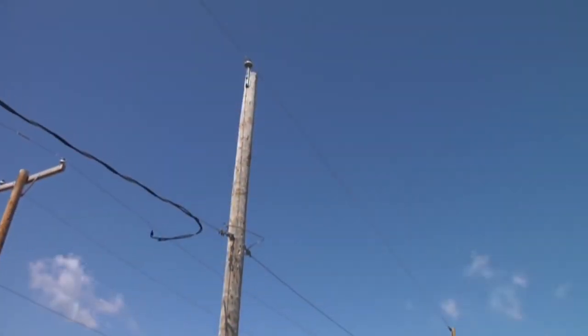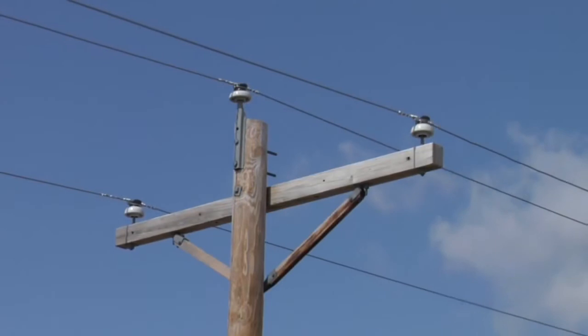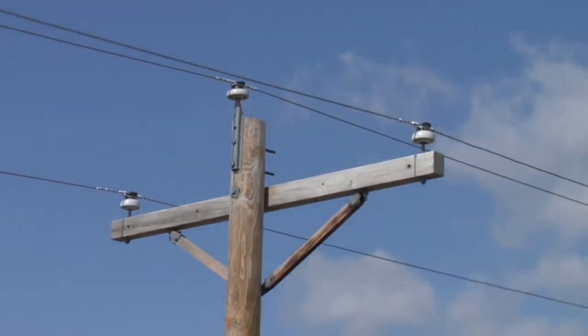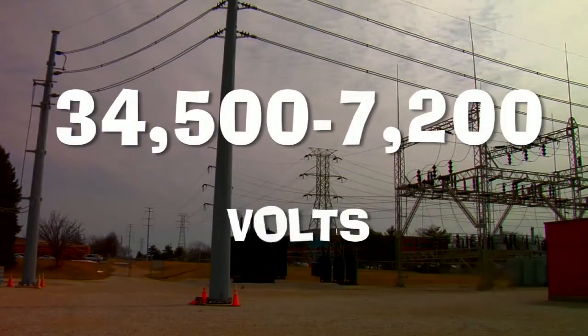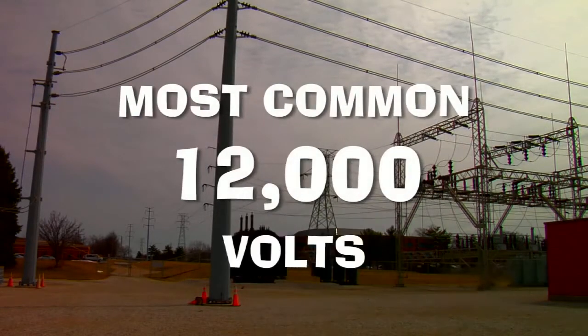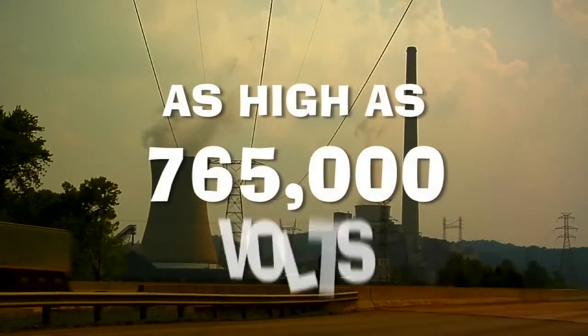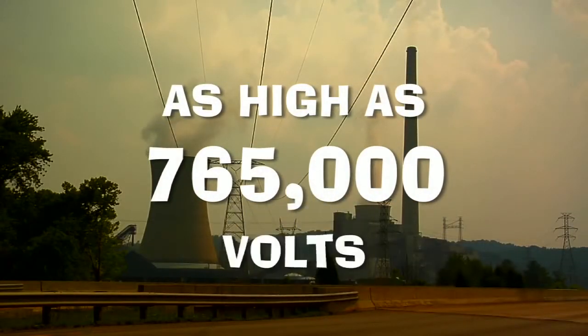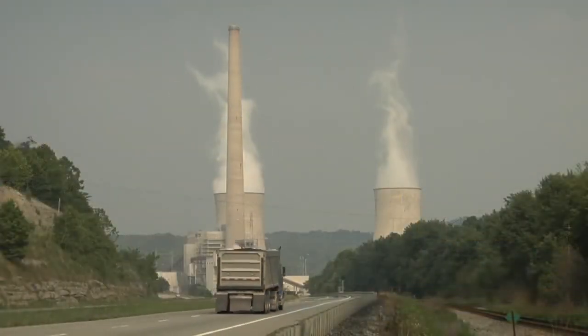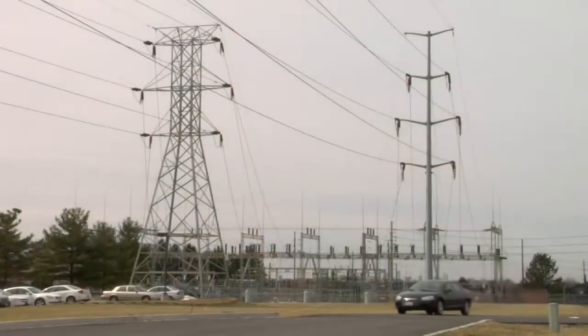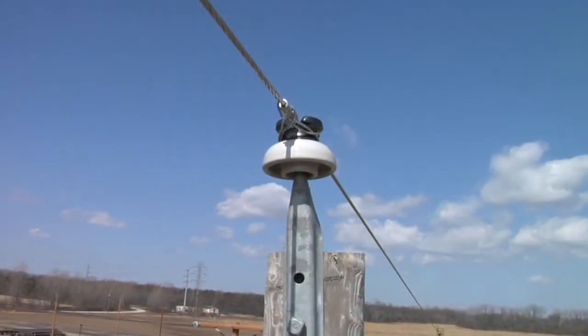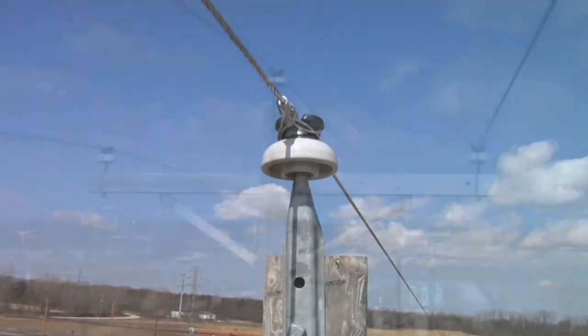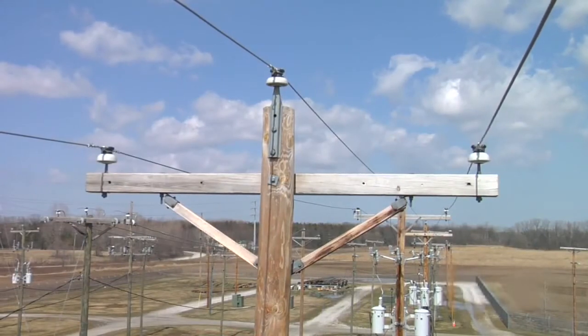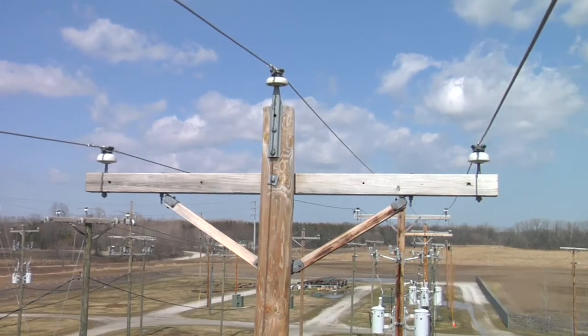At the top of the pole are the primary or main wires. These wires come from a nearby substation and can carry anywhere from 34,500 volts to 7,200 volts, with the most common voltage being 12,000. Remember, the electricity started out as high as 765,000 volts coming from the power plant and was stepped down to lower voltages at substations. If the electricity is going to a home, there is typically just one main wire. If it's going to a business, there are 3 wires, because a business usually needs and uses more electricity than a home.